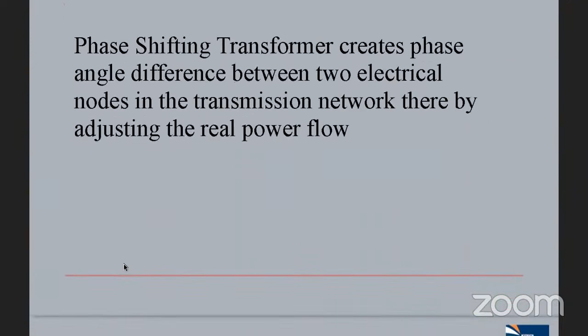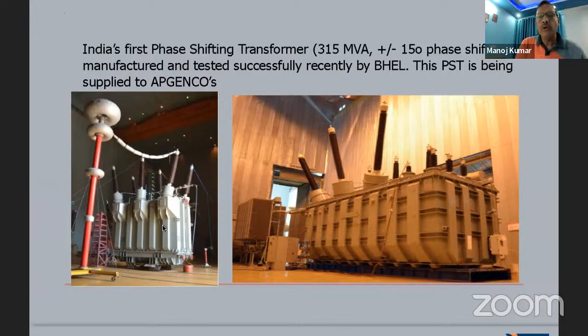These are the physical pictures of those transformers developed by BHEL. This is the series transformer unit. This is the shunt transformer unit. Those were tested specifically. These are their control windings. We are tapping the voltages from the control windings and putting them into the series winding, and we are adding a phase angle between the two ends of the transformer and controlling the power flow into the system.